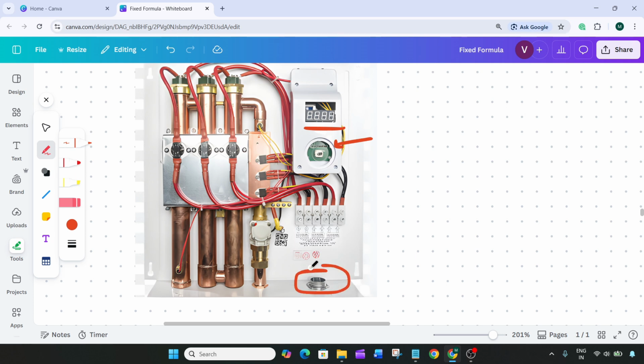and test again. If that doesn't work, do a manual reset by turning off power at the breaker, removing the front cover, and pressing the small reset button near the thermostat until it clicks. Reassemble the unit, restore power, and test hot water.